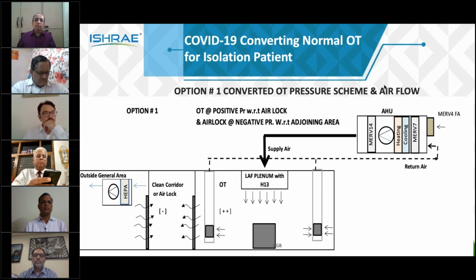One is converting the OT pressure in this way: you take a certain amount of air that is leaking into the clean corridor, you can see that, and then you put it outside into the general area through a HEPA filter. This is the one which is recommended by ASHRAE. So your pattern of flow as far as the operation theater itself remains positive. The clean corridor is under negative, so the outside area gets protected from the operation theater. We have got another option that is available. The next slide.